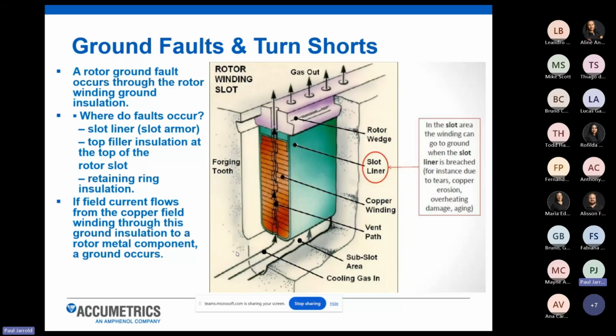So faults can occur in the slot liner. They can occur in the retaining ring on each end of the cylindrical rotor. There are different areas where that can happen. The main thing is that you need a system that's able to monitor the value of resistance in that copper bus bar over a long period of time. And you can predict when a ground fault is going to happen when you see the resistance of those windings drop.